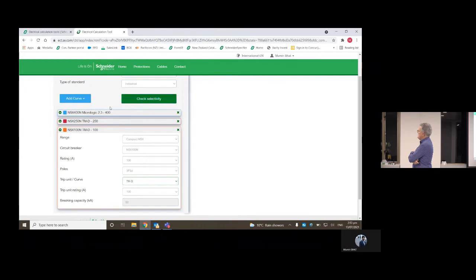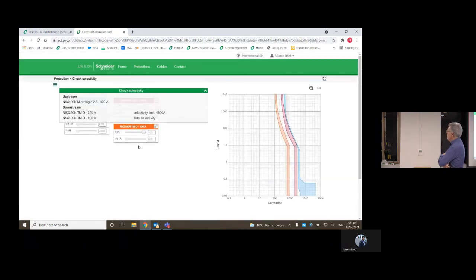And we check selectivity. And we're going to get a result here, which is not going to be 100% for us. But we've got selectivity limit up to 4,800 amps. And as we say, between the 400 and 250, but total between the 250 and 100, which is understandable because we're over 2 times there. So what are we going to do about this? What can we do?